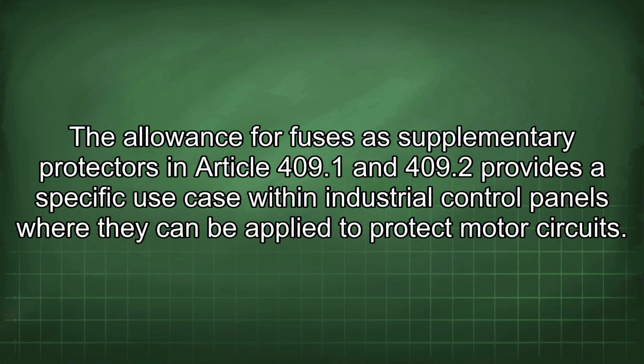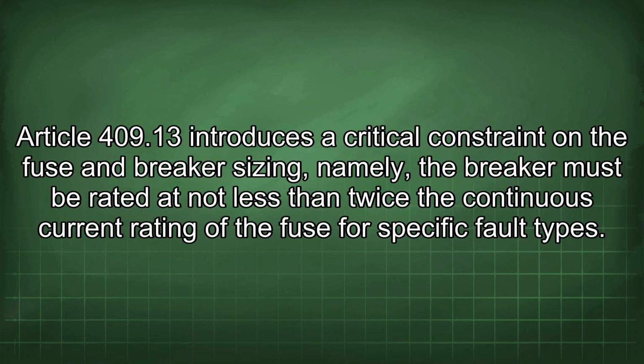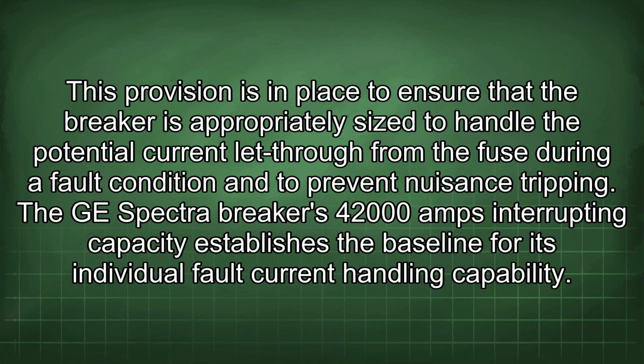The allowance for fuses as supplementary protectors in Article 409.1 and 409.2 provides a specific use case within industrial control panels where they can be applied to protect motor circuits. Article 409.13 introduces a critical constraint on the fuse and breaker sizing, namely, the breaker must be rated at not less than twice the continuous current rating of the fuse for specific fault types. This provision is in place to ensure that the breaker is appropriately sized to handle the potential current let through from the fuse during a fault condition and to prevent nuisance tripping. The GE Spectra breaker's 42,000 amps interrupting capacity establishes the baseline for its individual fault current handling capability.